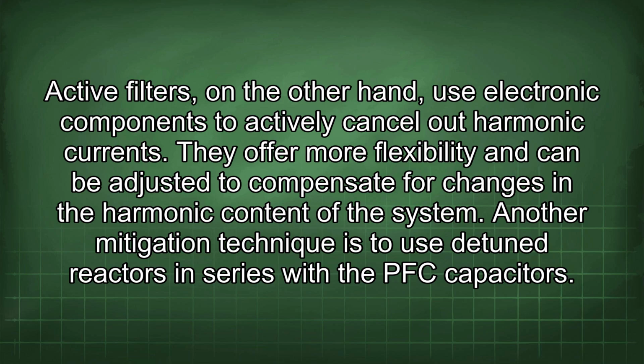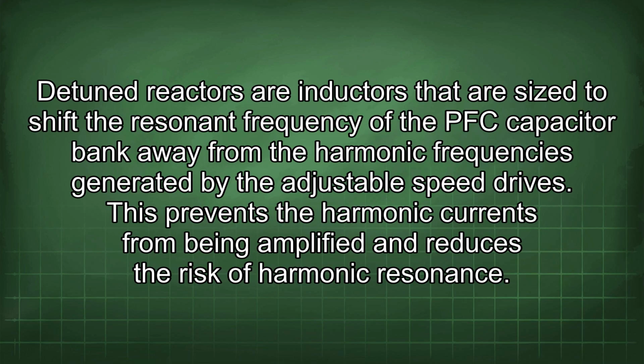Another mitigation technique is to use detuned reactors in series with the PFC capacitors. Detuned reactors are inductors that are sized to shift the resonant frequency of the PFC capacitor bank away from the harmonic frequencies generated by the adjustable speed drives. This prevents the harmonic currents from being amplified and reduces the risk of harmonic resonance.